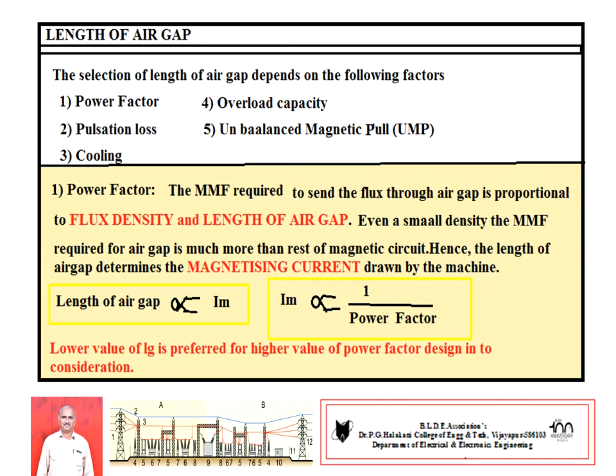So you remember 2 blocks. One block: length of air gap is directly proportional to magnetizing current. Magnetizing current is inversely proportional to power factor. What it means is, if the designer uses a smaller value of length of air gap, it results in a lesser value of magnetizing current. This lesser value of magnetizing current increases the power factor. You have to remember only 2 blocks. Hence, a lower value of LG will be preferred for design of a higher value of power factor.